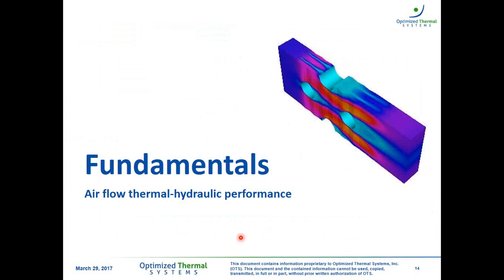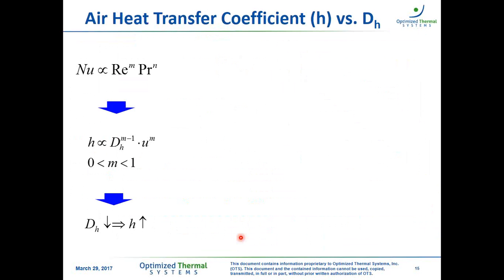Now let's talk about the performance, starting with the airflow thermohydraulic characteristics as we change the tube diameter. So now I'm not talking about heat exchangers, but from a fundamental aspect of the tube diameter itself. If we look at the relationship between the non-dimensional numbers, especially Nusselt and Reynolds numbers, and derive the above equation, one will find out that the heat transfer coefficient indicated by h is inversely proportional to the hydraulic diameter of the tube. So the relationship is hydraulic diameter to the power of m minus 1, where m is usually a number between 0 and 1.